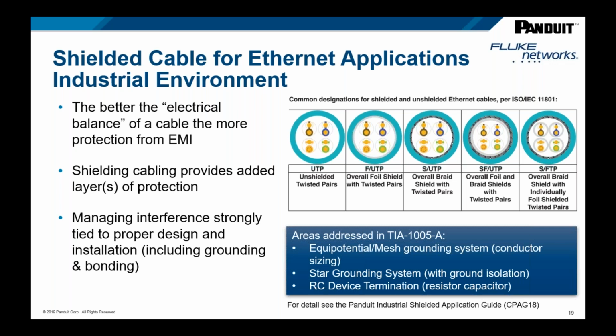There are also braided versions of these shielded cables. The braid relates to increasing the surface area on the shield and providing a low resistance path to drain out high frequency noise. The additional layers of shielding also provide additional noise protection. I'm not going to go too far into grounding and bonding, but highlighting for you in the blue box, the TIA 1005A does recognize the grounding and bonding system in three different areas. The equipotential and mesh grounding system, and it refers to the conductor sizing. It has the diagramming for the star grounding system, which is an isolated ground. And then it also defines an RC, or resistor capacitor device, termination. There is a white paper which will provide you that goes further into these topics.